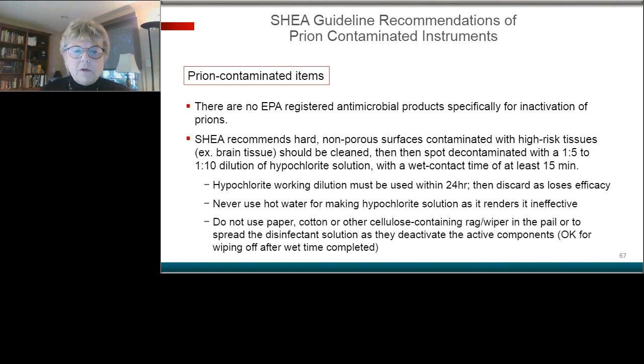The hypochlorite working dilution must be used within 24 hours. That's always, not just for prion, and then discarded as it loses its effectiveness. Never, and I'm going to emphasize this, a lot of people haven't heard this one, never use hot water for making hypochlorite solution, as it renders the chlorine ineffective. That's at home too, where we tend to think hot water is going to help a lot of things. Not in this case.